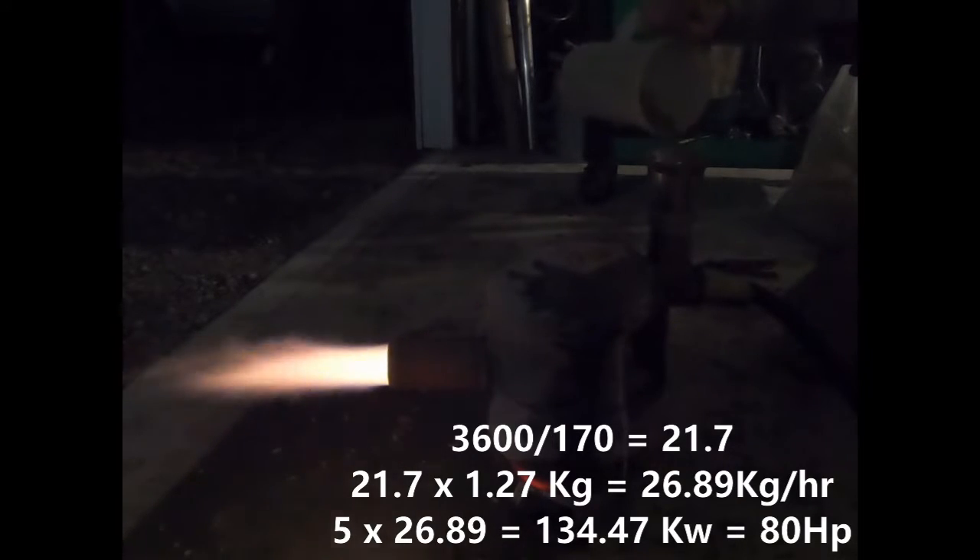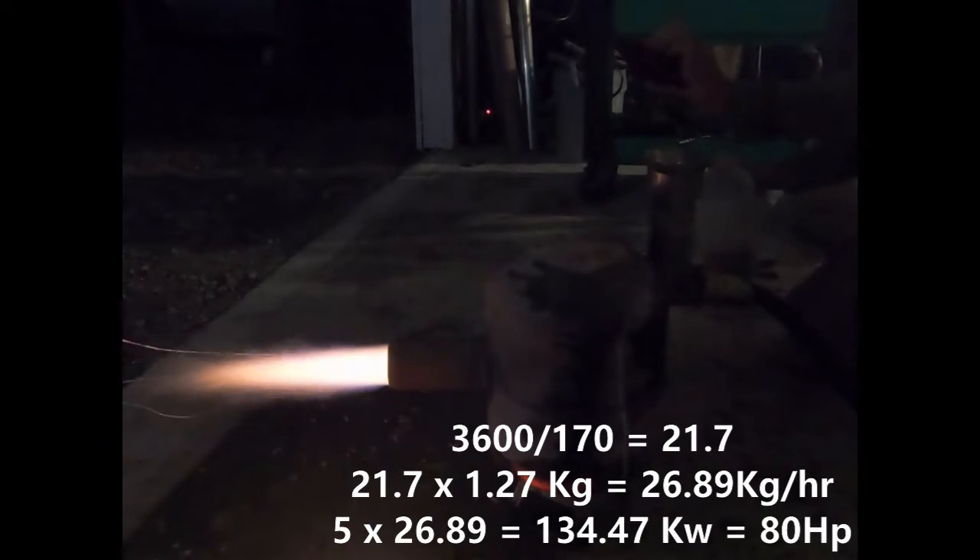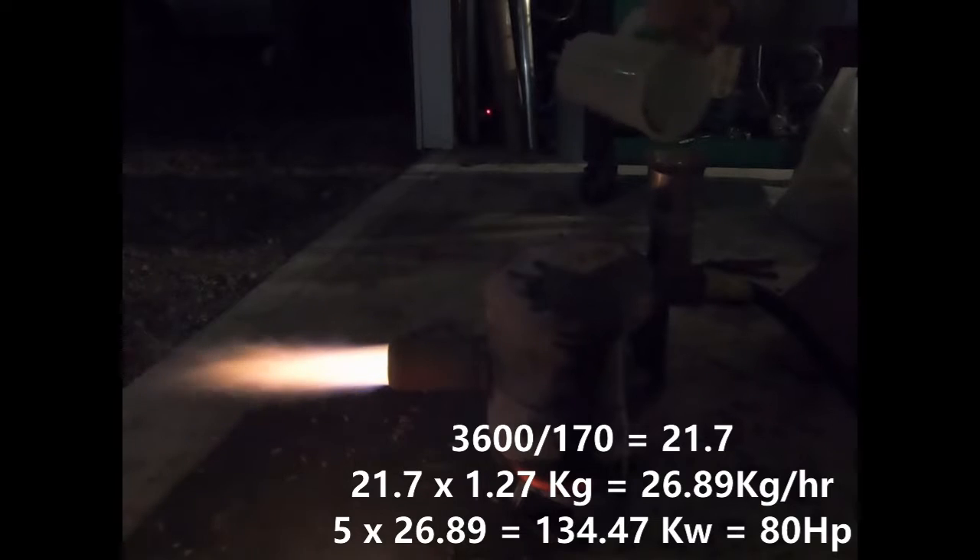I found myself in need to catch up several times. However, my concern with the overfeeding is that the charcoal has a higher residence time than the actual wood burn portion of the deal. The little charcoal pellets tend to hang around for quite a long time. A scenario could unfold where it would appear you're not overfeeding it, but then you just end up with all this charcoal that just won't burn fast enough. Because we are so far above the 64 kilowatt target, that gives us plenty of room.